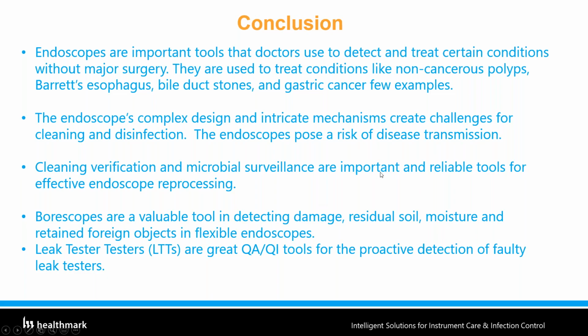Clean verification and microbial surveillance, as I indicated: when they were doing the testing, sometimes we didn't know if the failure of those microbial tests was a result of the environment or the process that we took. Obviously, if you want to make sure there's nothing, you should do some of the procedure in a clean operating room. But if you don't have that flexibility, or it's not available, or people are not willing to go after hours or on the weekend, you're going to have some issues.